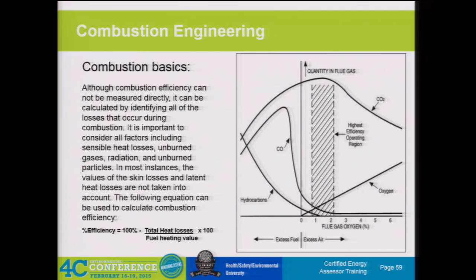This is another look at the relationships on the graph. This is kind of the peak efficiency region—where the CO2 peaks out. The other components we're measuring in the stack: we've got CO, which is one big indicator. The CO level is driving down towards some much lower level approaching zero. And then our hydrocarbons—or unburned fuels—having that additional analysis in the stack helps us understand where we are in this relationship. In theory, we should have that unburned fuel down to zero when we find that sweet spot for the air-to-fuel ratio. That air adjustment is this oxygen content right here.